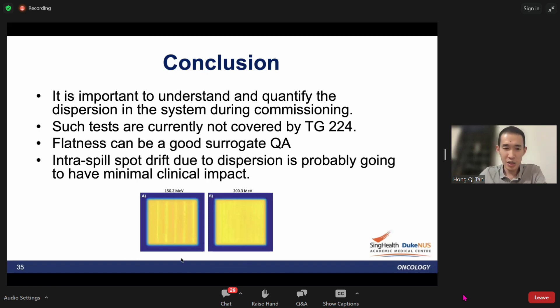As mentioned, flatness can be a good surrogate QA. At the start, when the beam was not very flat with dispersion and spot position drift during the spill, we got spot profiles that looked pretty bad. You can use this to gauge the intra-spill spot position deviation, but it's not a quantitative way to measure dispersion or spot position deviation.